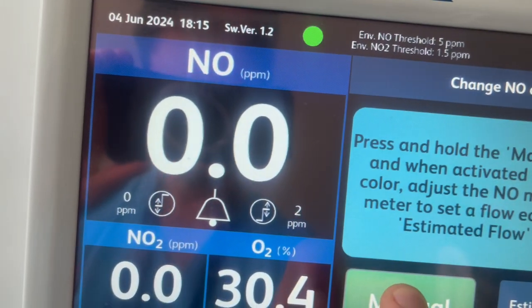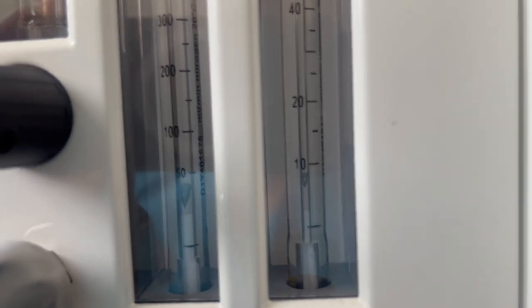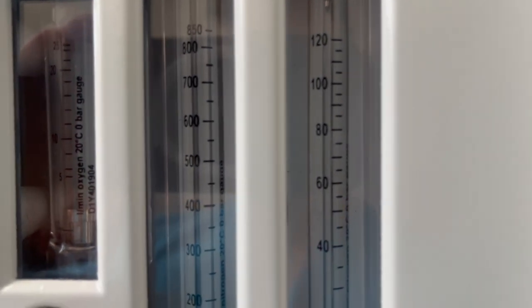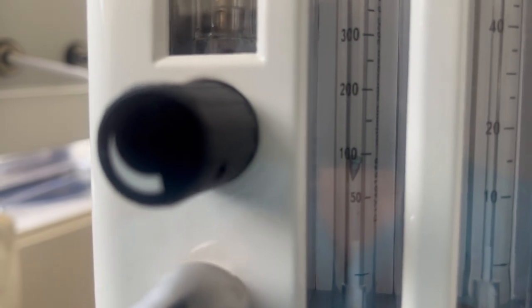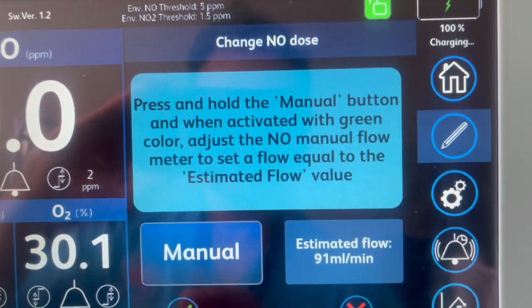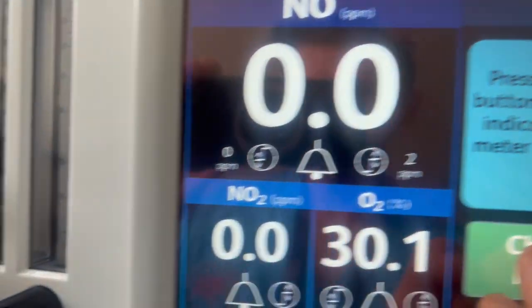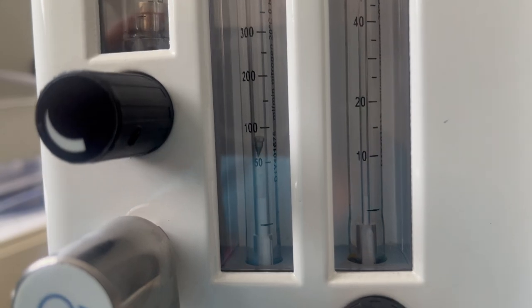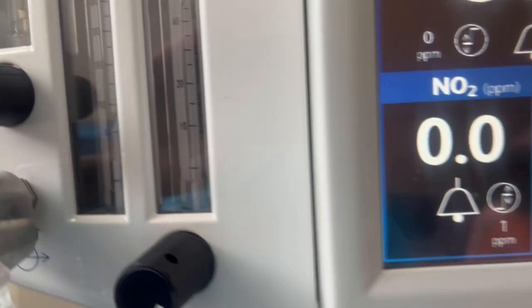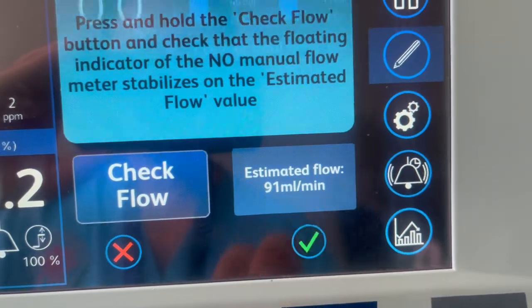By keeping your finger pressed down on the manual icon, and with your other hand, you can turn the NO flow meter to set the estimated flow. Moving from one flow meter to the other flow meter. And so you can achieve as close to the estimated flow as possible. And then confirm. The check flow will again let you check that it is as accurate as possible. And then confirm.